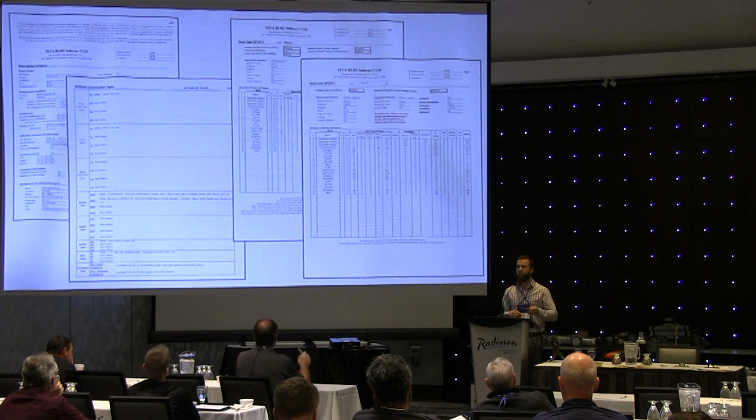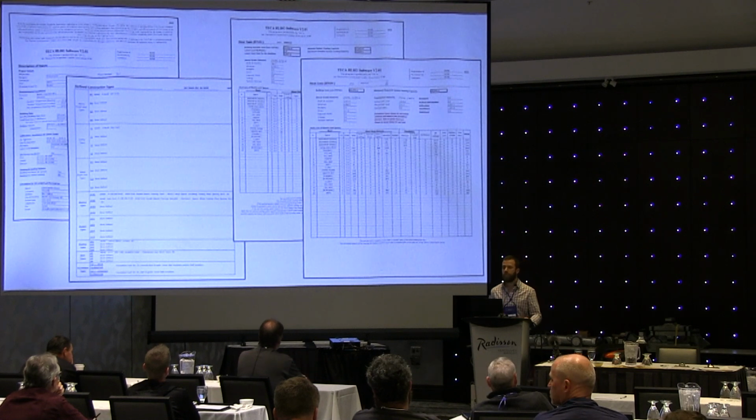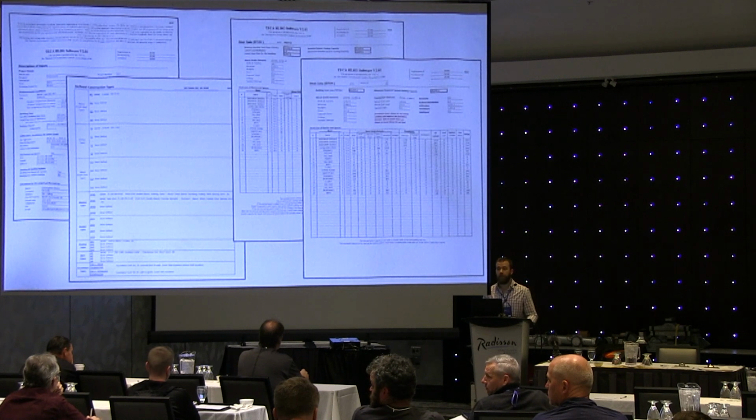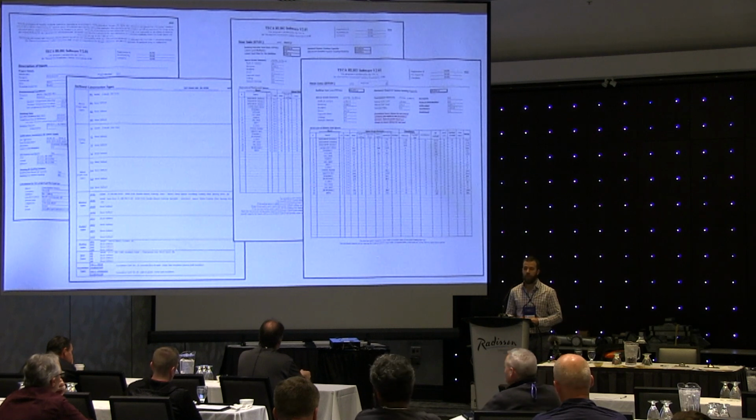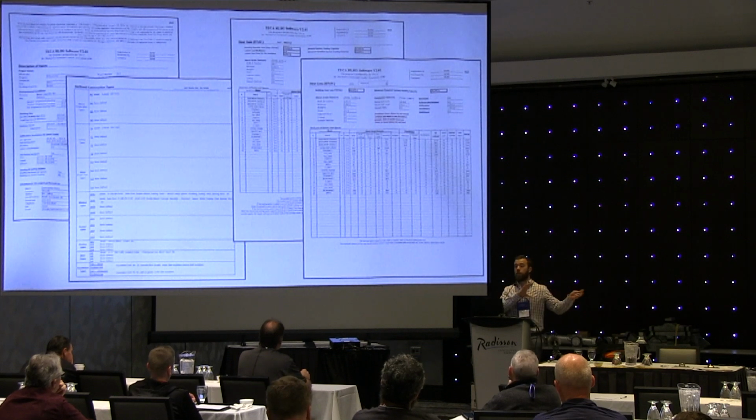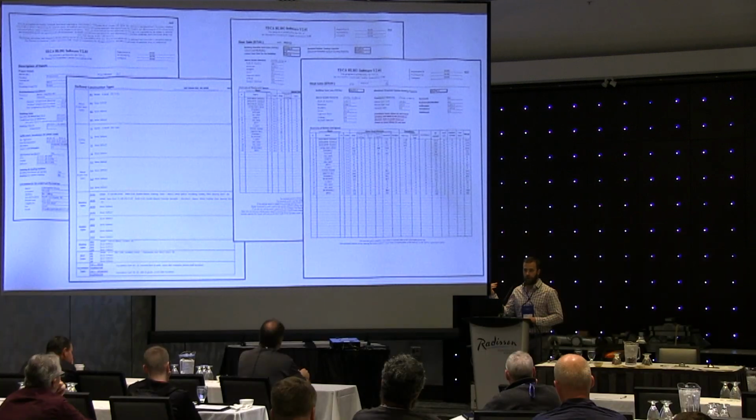So when you're choosing your locations, is it just the ones that are in the code, the very general ones? There's so many sub-areas that have different conditions. Great question, thank you. We took this whole list from CSA. That's all they've defined. Let's say you're searching for a region or city that's not on the list. You would choose the closest geographical city for latitude and longitude, and then you would input local conditions, right? The local temperatures of the air and soil if you have it.